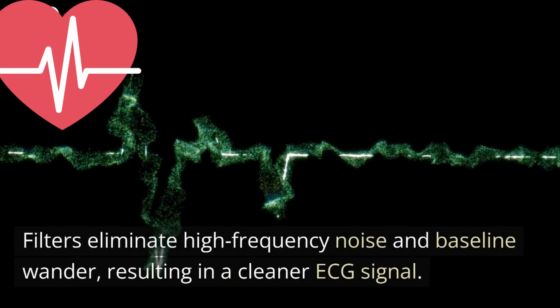Number 4. Signal conditioning and filtering. The electrical signals may contain noise or interference caused by muscle movement, patient movement, or external factors. The ECG machine applies filters to remove unwanted noise and artifacts while preserving the essential cardiac signals. Filters eliminate high-frequency noise and baseline wander, resulting in a cleaner ECG signal.